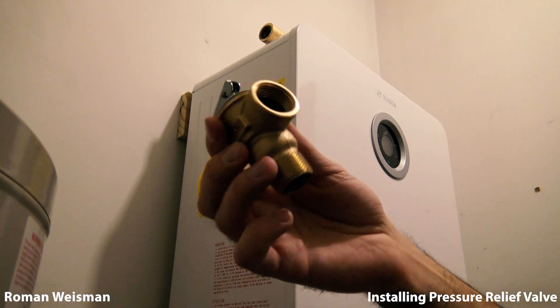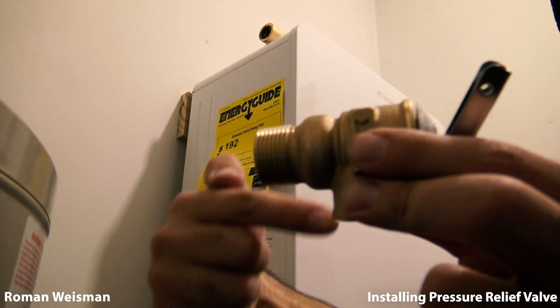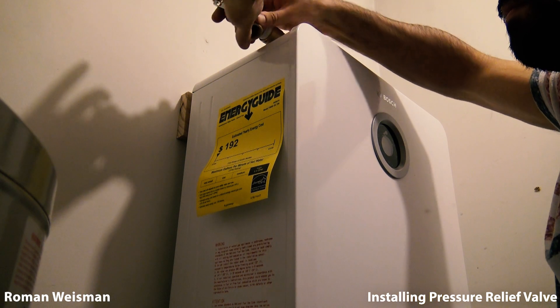This pressure relief valve comes with the unit. Some states require a T&P valve — the max input BTU of the unit must be lower than the max input on the valve. Doing clockwise and trying to leave one or two threads untouched to minimize the chance of teflon debris reaching the unit.